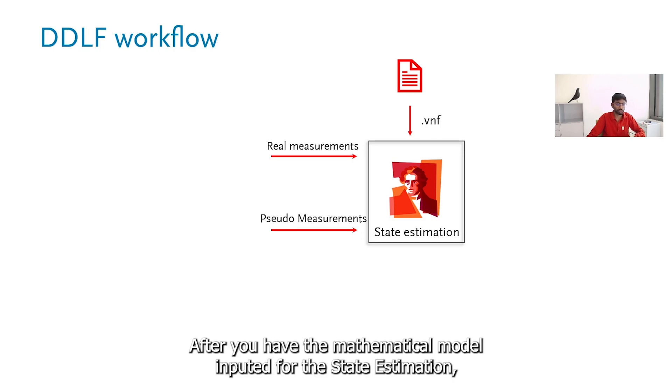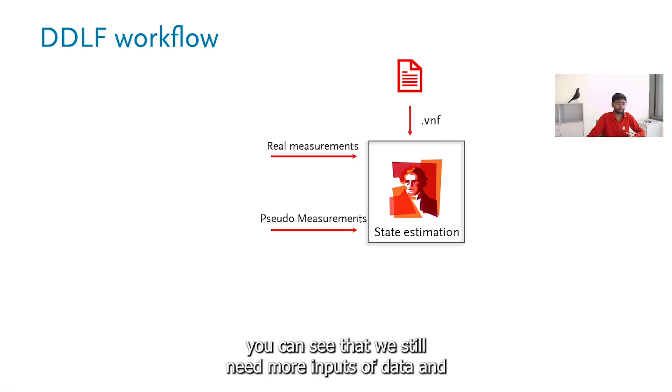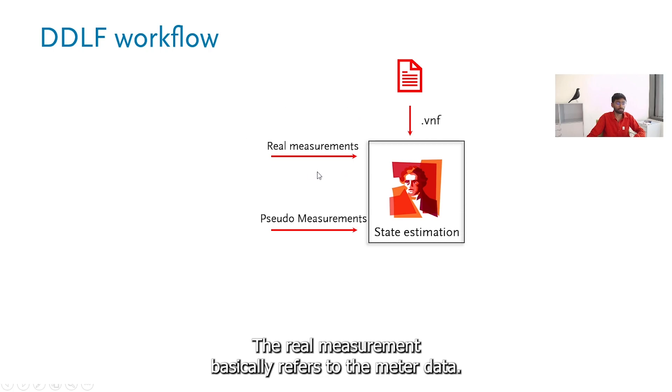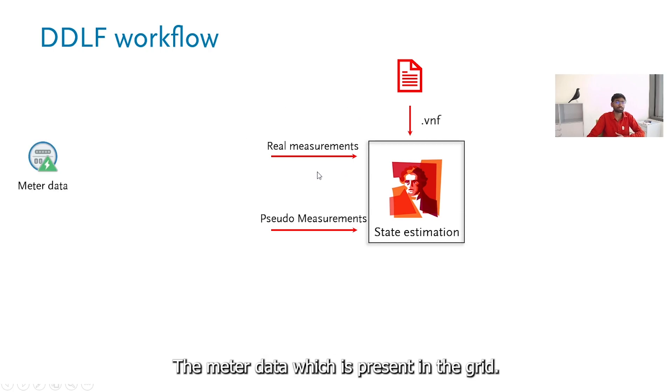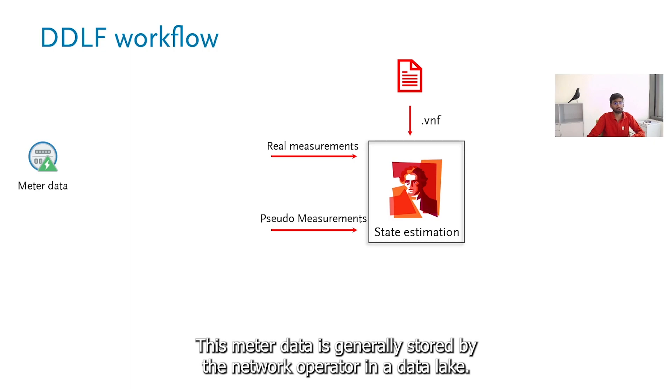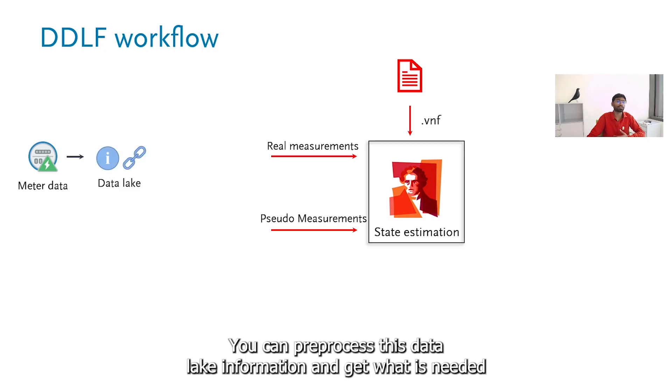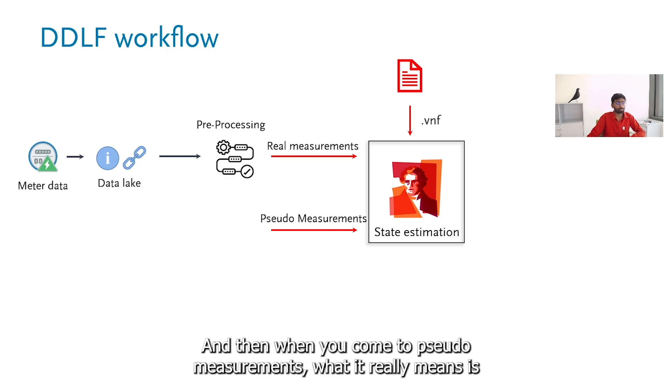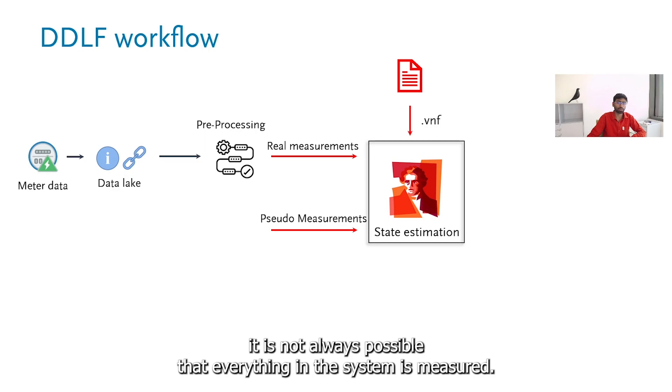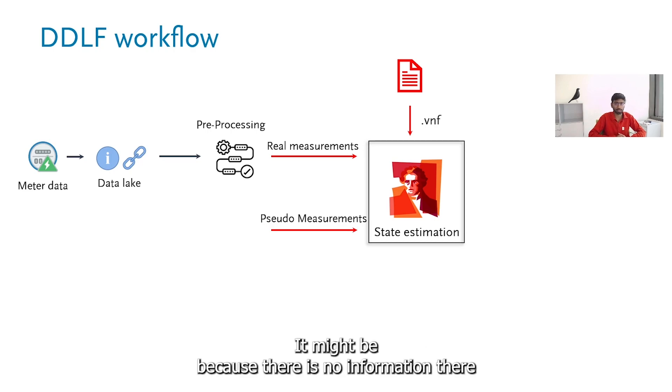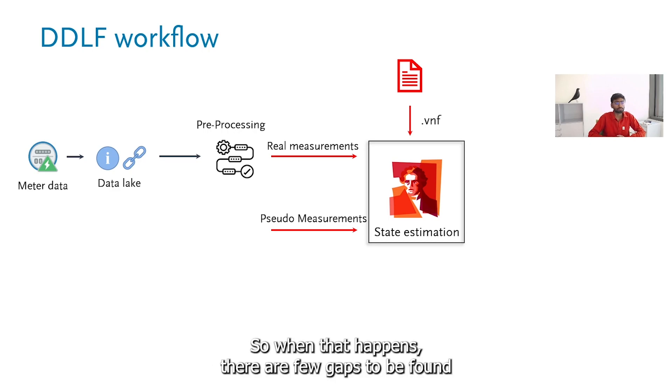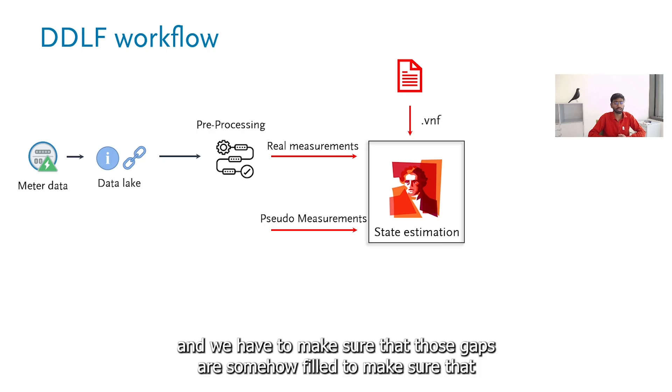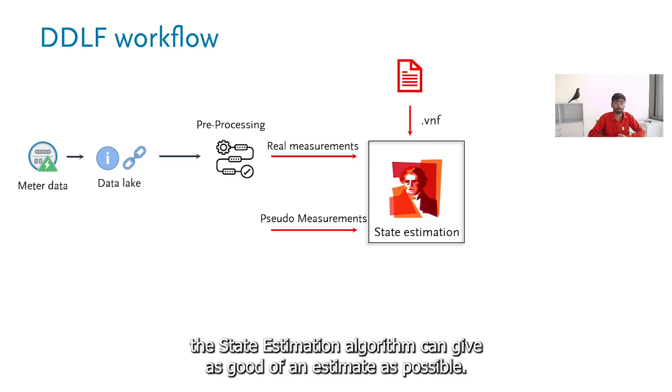After you have the mathematical model inputted for state estimation, you can see that we still need more inputs of data. That here is basically in the form of real measurements and pseudo measurements. The real measurement refers to the meter data which is present in the grid. This meter data is generally stored with the network operators in a data lake. You can pre-process this data lake information and get what is needed for this particular network and give it as an input to state estimation. When you come to pseudo measurements, it is not always possible that everything in the system is measured. It might be because there is no information there or there is a data glitch or some data mishandling. When that happens, there are few gaps to be found. We have to make sure that those gaps are somehow filled to make sure that the state estimation algorithm can give as good of an estimate as possible.